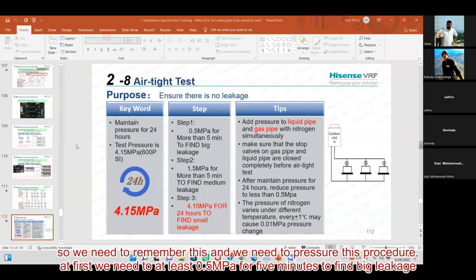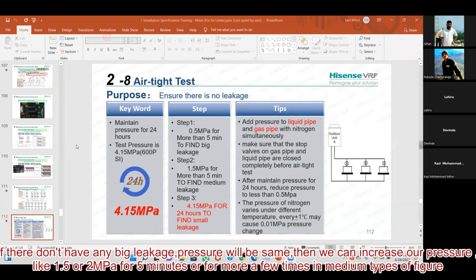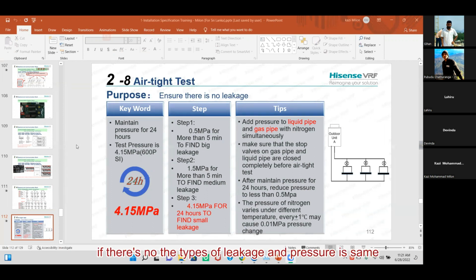Now the pressure test procedure. At first, we need to pressurize at least 0.5 megapascal for 5 minutes to find big leakage. If there is no big leakage, then the pressure will stay the same. Then we can increase our pressure, like 1.5 or 2 megapascal for 5 to 10 minutes or more, a few times, for medium types of leakage.